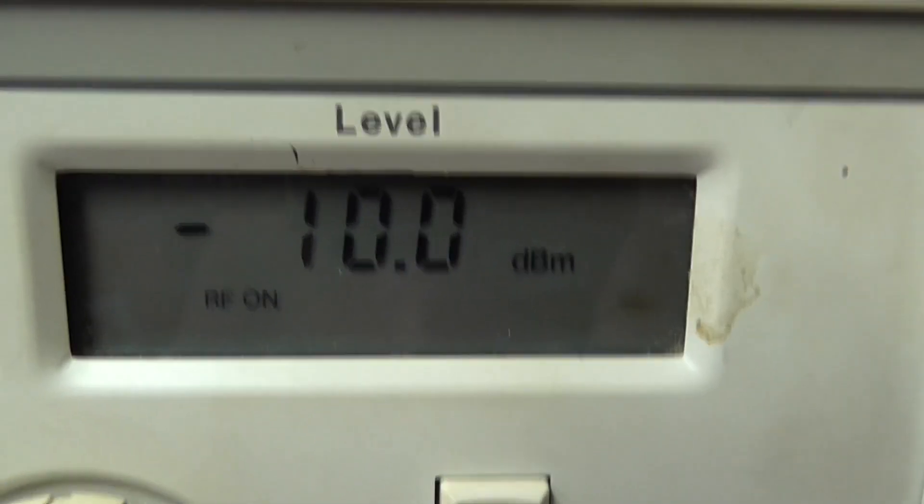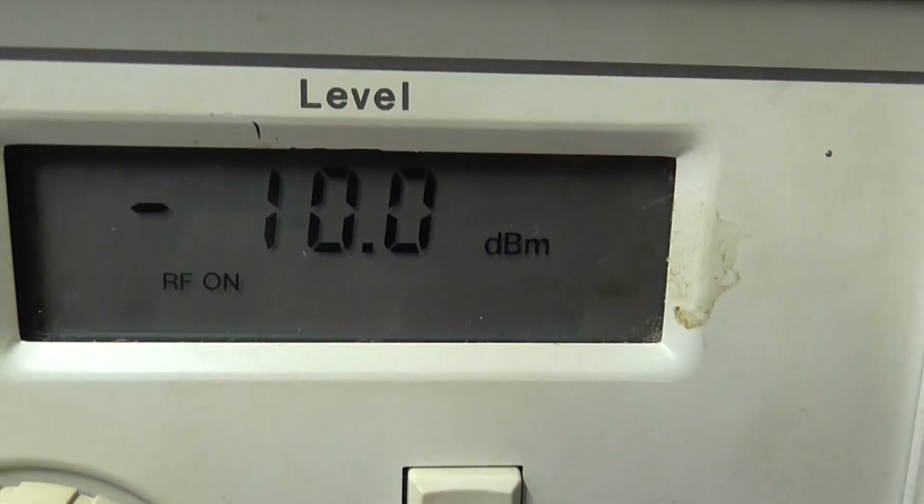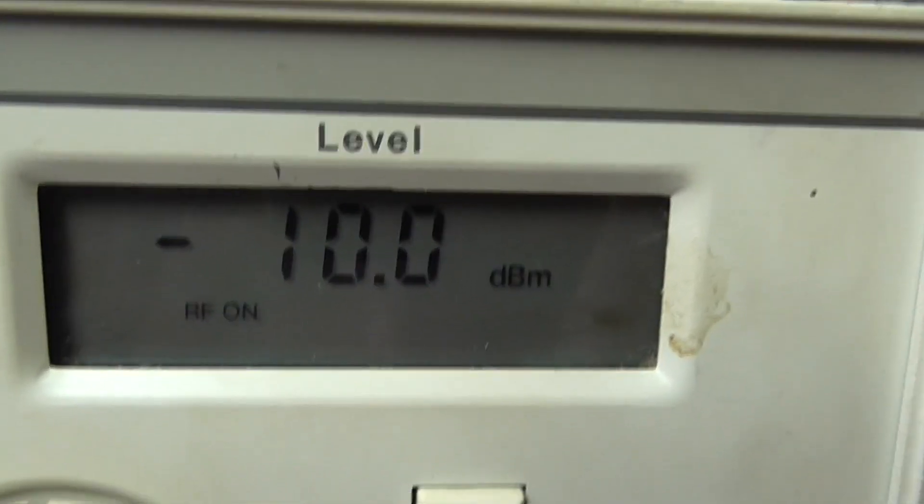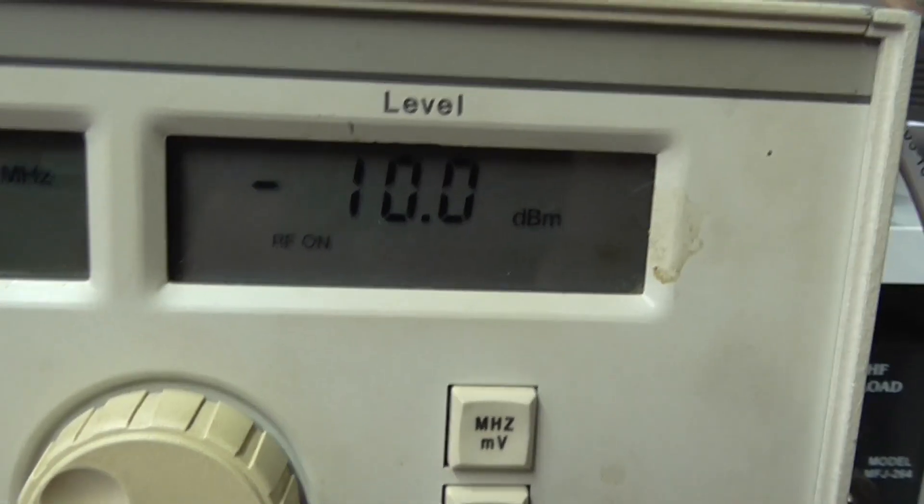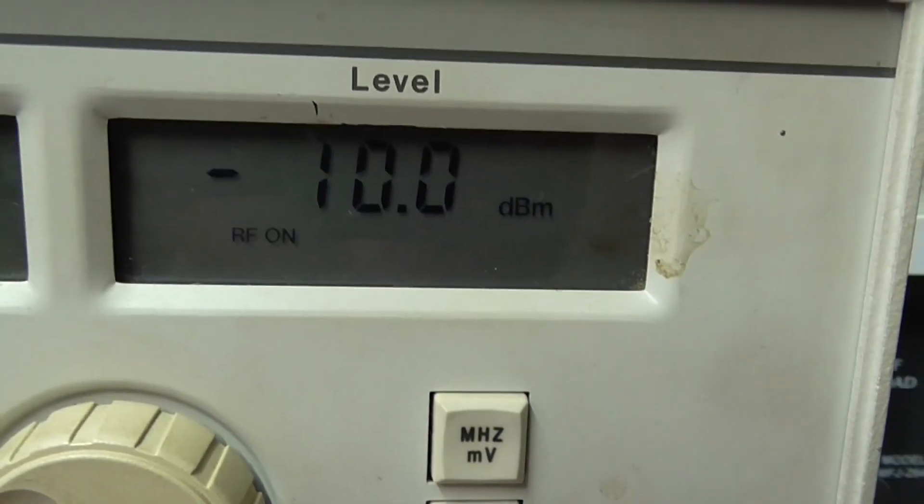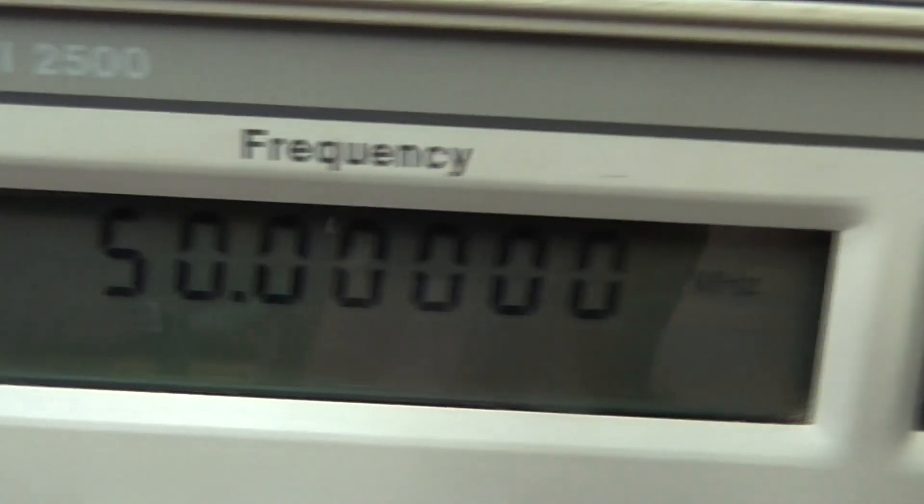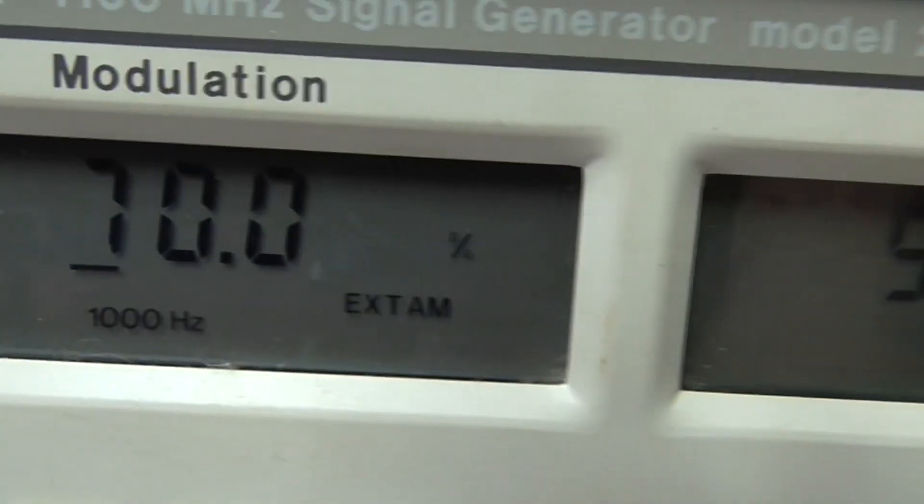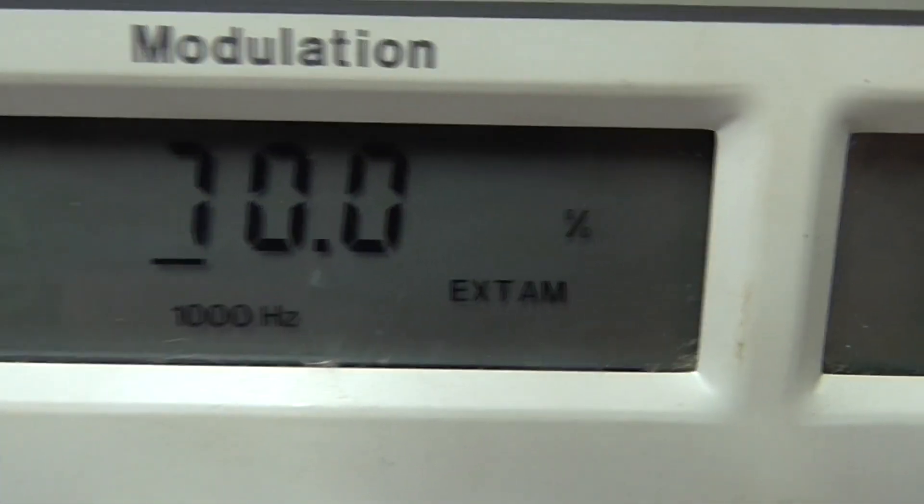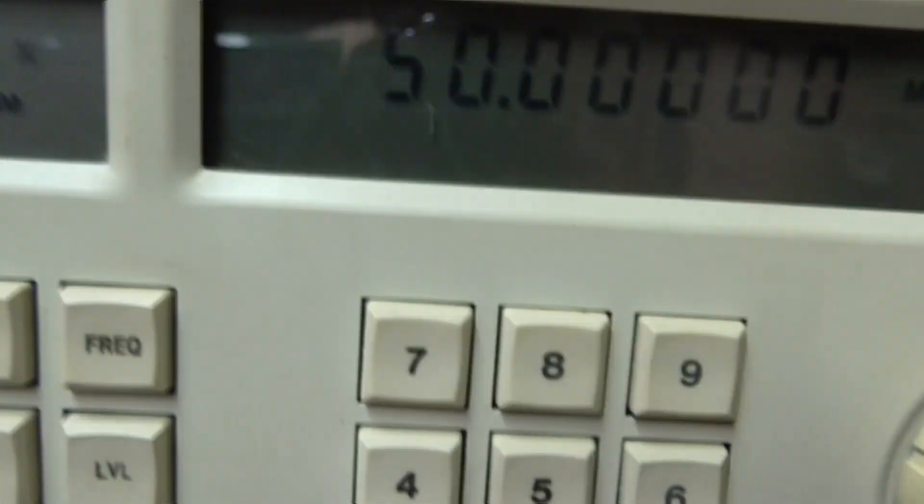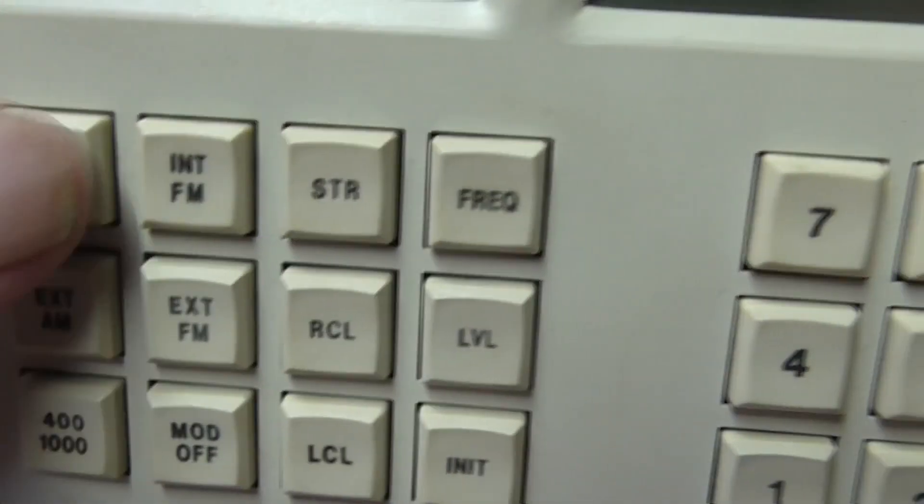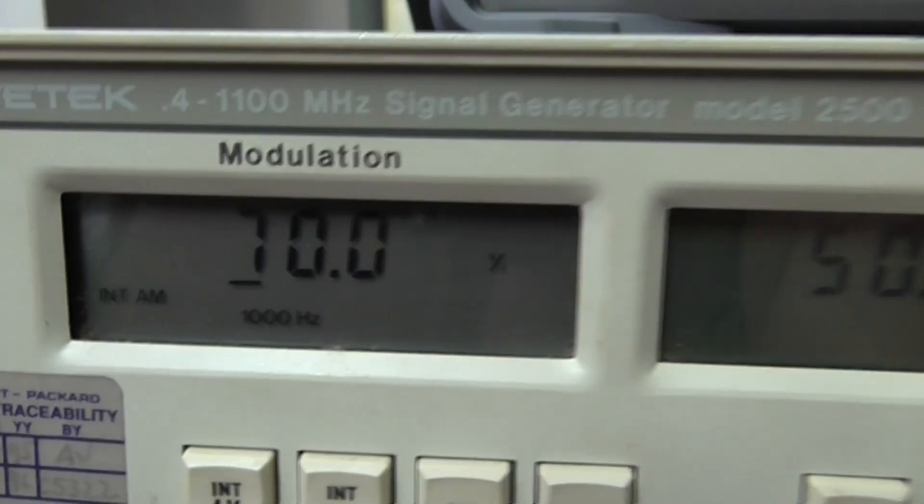We're going to have an output of minus 10 dBm and we're going to play with two-tone generators. At the moment you'll see we're set to external AM. We'll switch it to internal AM.